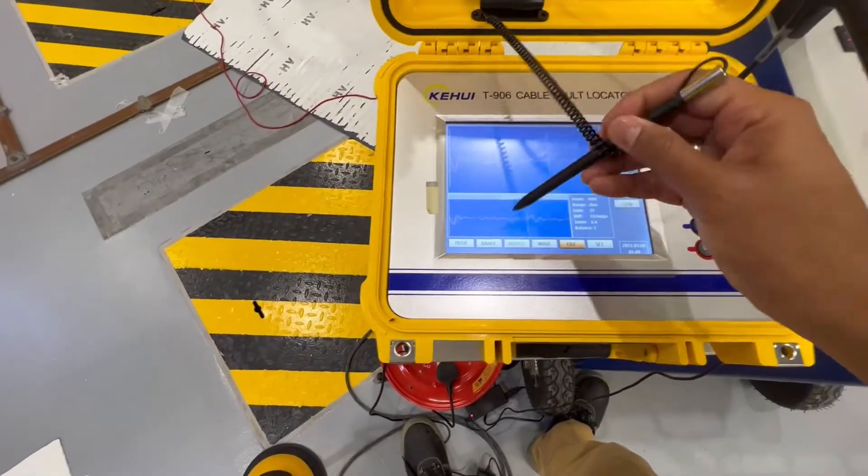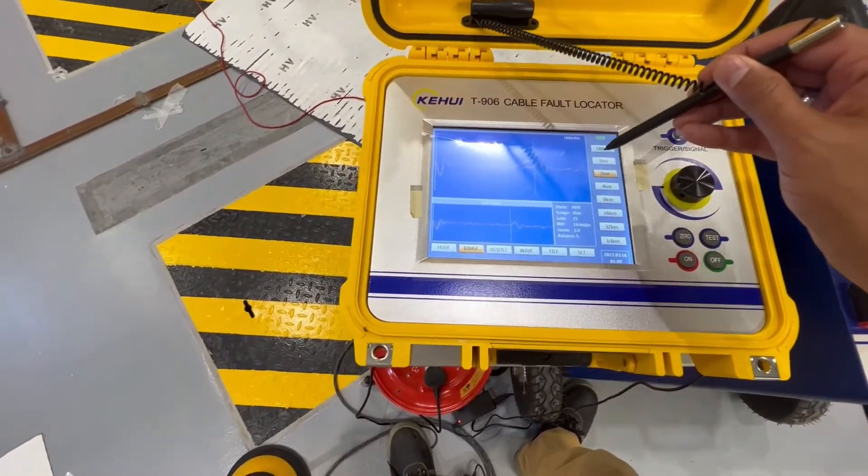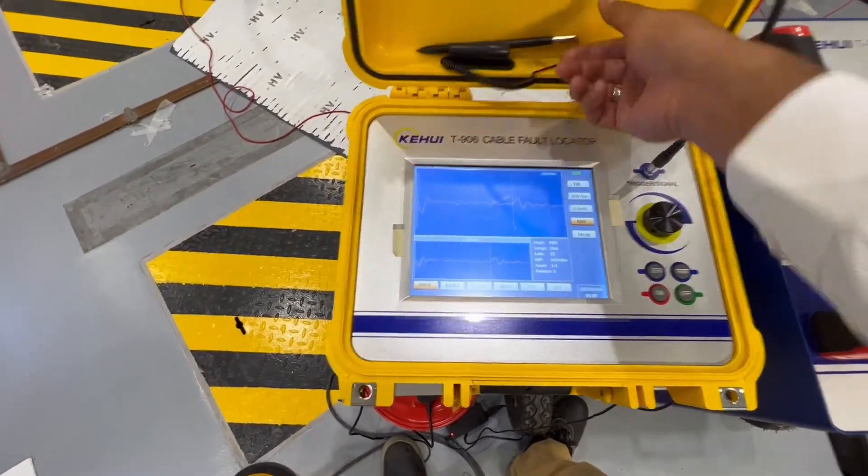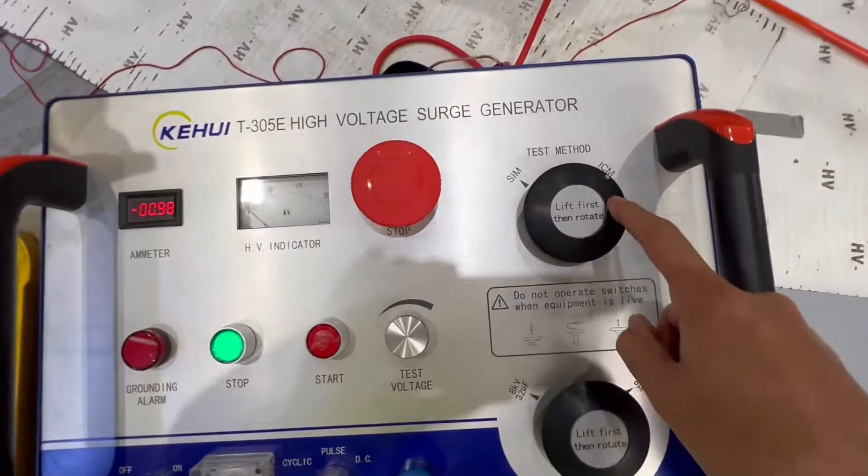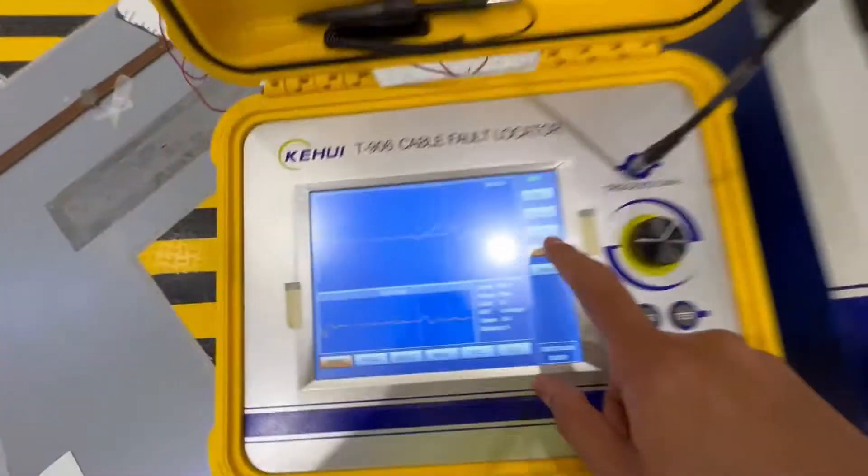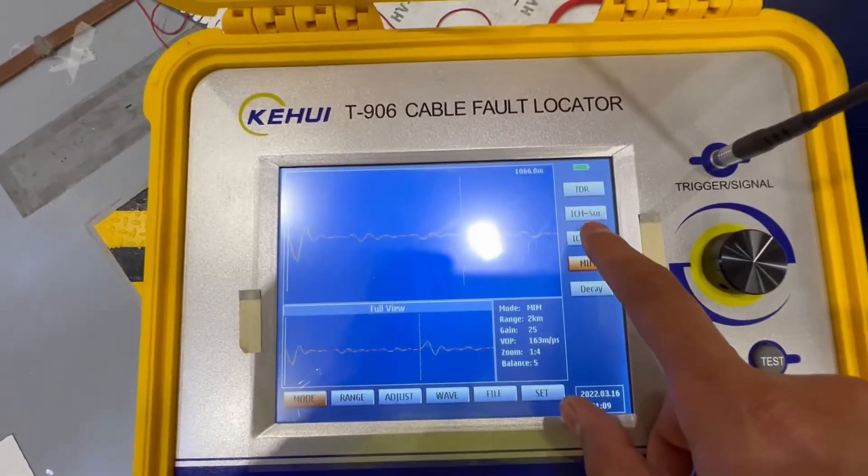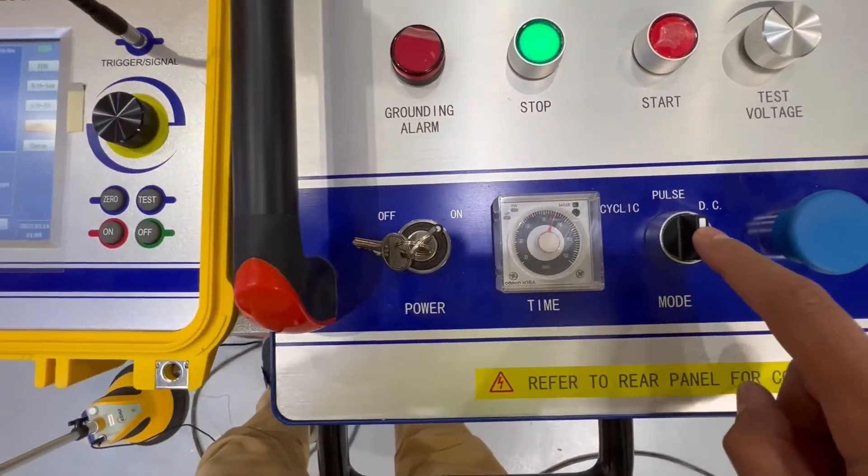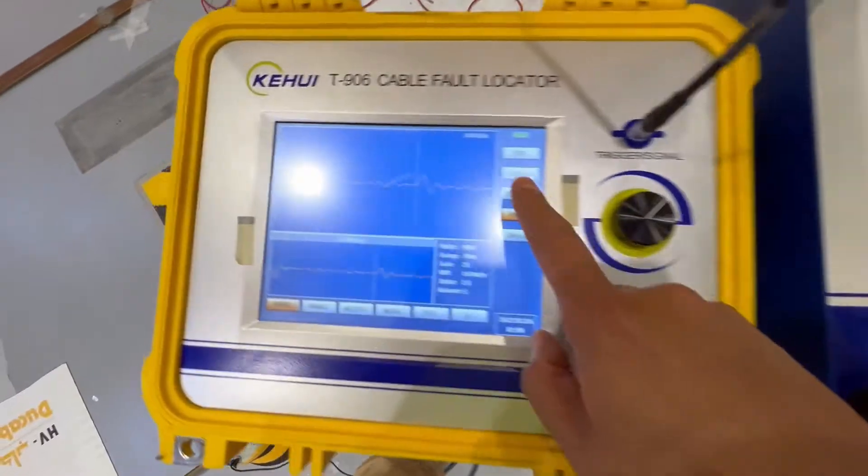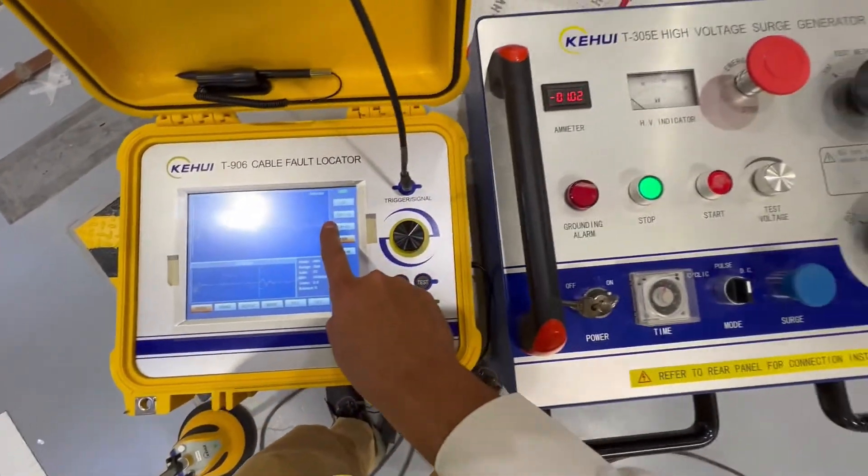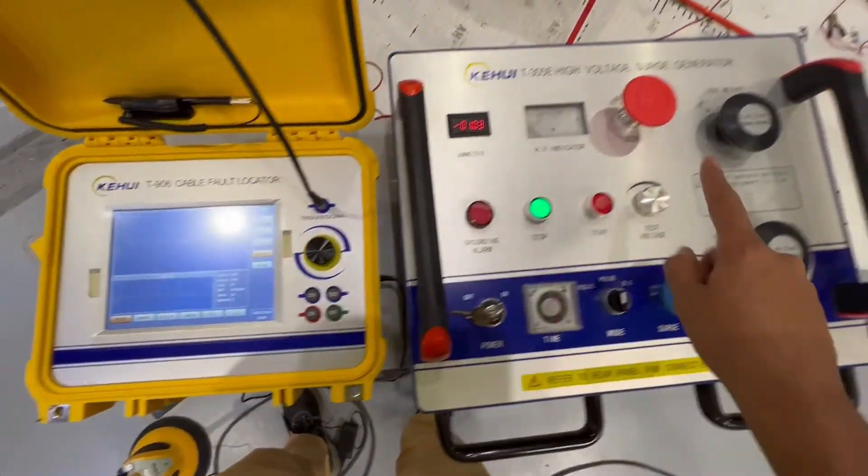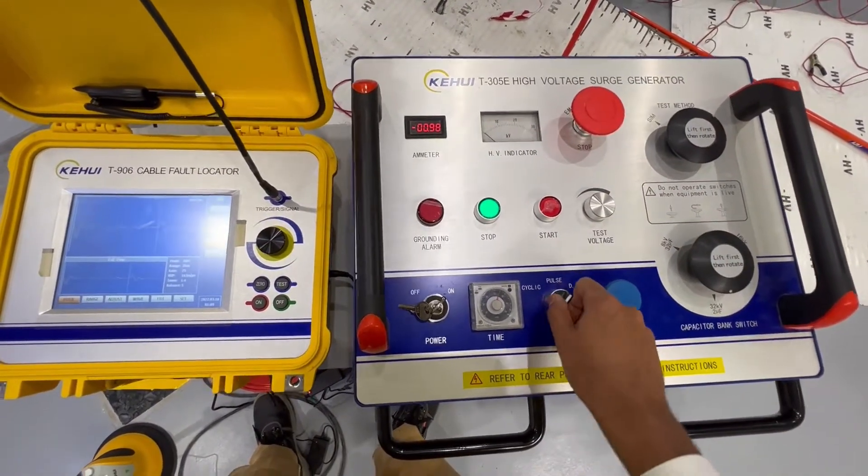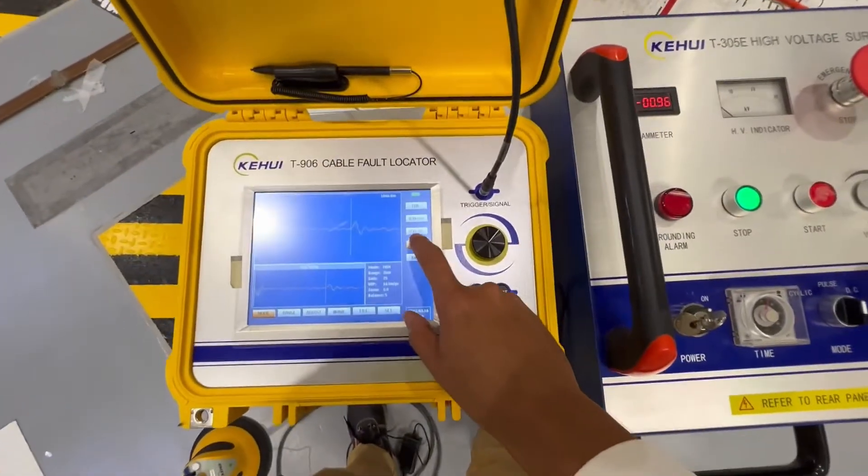You select the range, 2 kilometers, and then select the mode. If you want to do ICM method from the surge generator, you have to select ICM surge. ICM surge is only for a single pulse. If you want to have ICM DC, the test method will be ICM and the mode will be DC.